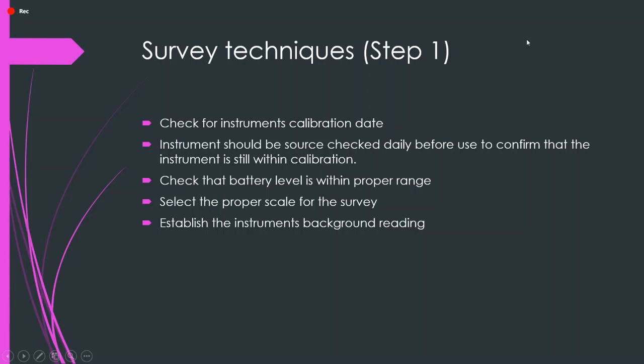Then we should make sure that it has been source checked. Meters should be source checked daily to make sure that they are maintaining their calibration. Things can happen, and they can go out of calibration earlier. One reason could be that some kind of damage occurred that wasn't known about, like it got knocked over, or it fell, or it got hit by something accidentally. Damage can throw it out of calibration, or just little things. So it's always good to make sure that it's within its operating limit, and that's how we use the source checks. I do them at the EHS office once a day, especially when I know the meter is going to be in use. We also maintain 2 safety meters there.